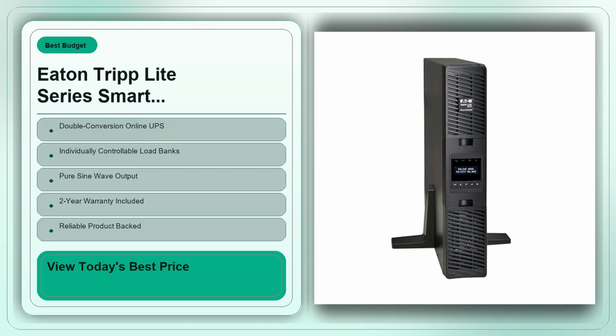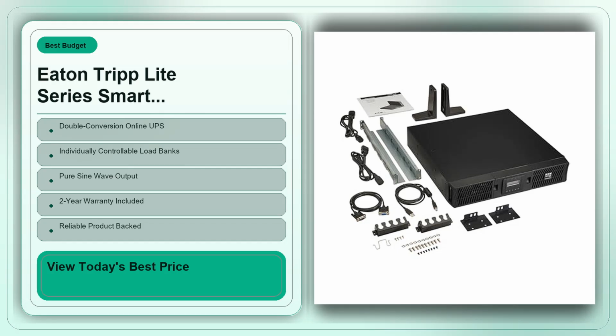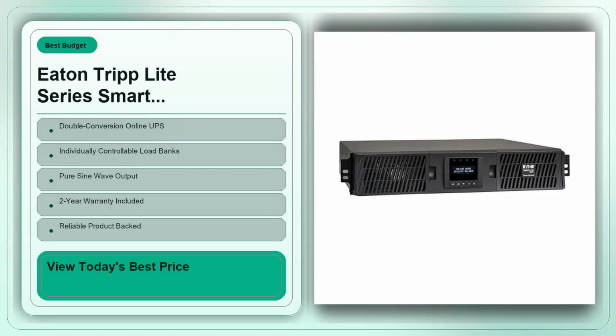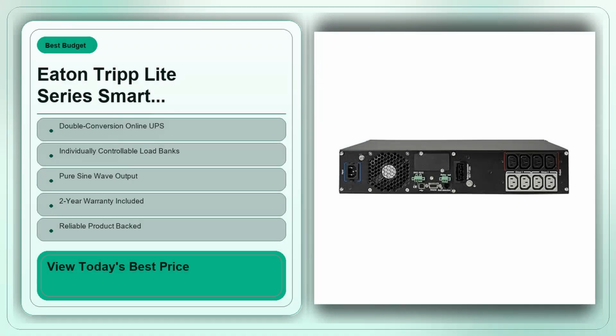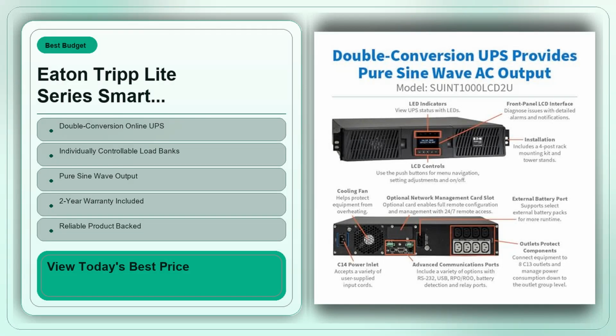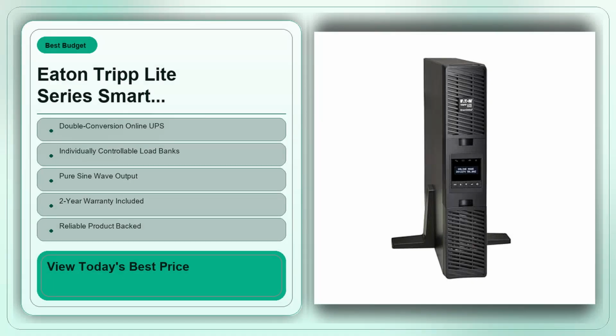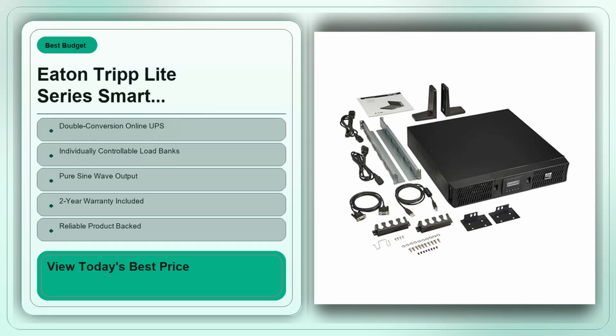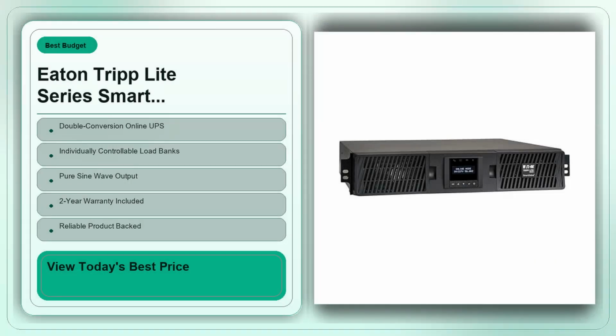Now, the hidden trade-offs. The most common complaint about online UPS units at this size is the heat they generate. Because the power is always being conditioned, the chassis runs warmer than a line interactive model would. In a tightly packed rack without adequate airflow, you might notice your ambient temperature creep up a few degrees, which could affect other equipment that's sensitive to heat. The fan noise, while not deafening, is audible if the rack sits in a quiet office or a home studio. It's not a problem for a server room that already has humming equipment, but it's something to keep in mind if you need a silent environment.